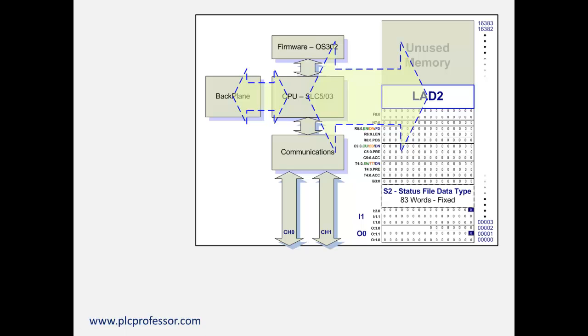Here we have a complete diagram for a programmable logic controller — not a programmable automation controller using the Logix engine, but the older family of processors. We have memory RAM, and in there we see the basic structure for SLC 500 and MicroLogix. We have output and input tags, timers, counters, control, integers, and floating point. We also have ladder 2, which is the actual program, and S2, the status file. Data flow to and from memory is controlled by the CPU, which has a supervisor called firmware.